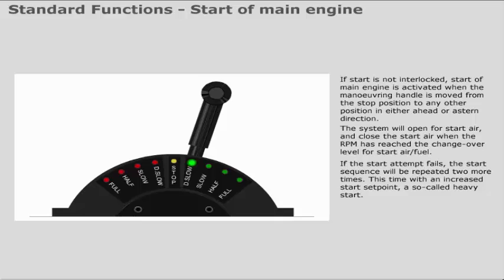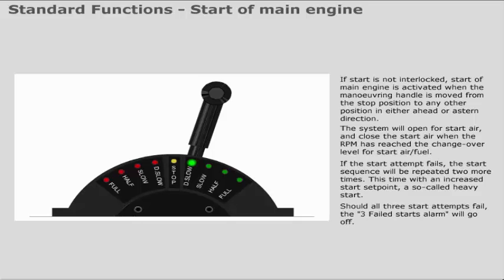If the start attempt fails, the start sequence will be repeated two more times. This time with an increased start set point, a so-called heavy start. Should all three start attempts fail, the three failed starts alarm will go off.